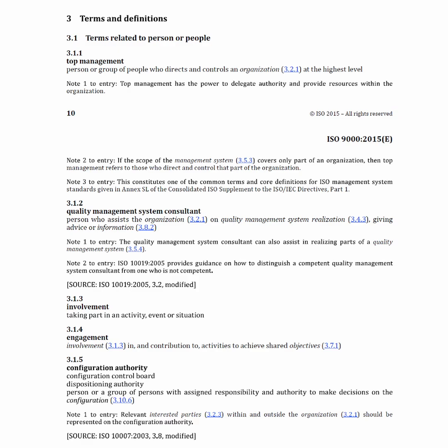Now, although the FDA is using ISO 13485 as the backbone of the new requirement, it is important to note that several components of 21 CFR Part 820 are still applicable. In addition to ISO 13485, manufacturers should also be aware that aspects of ISO 9000, specifically the terminology and definitions found in Clause 3, are also referenced within ISO 13485. So, as a manufacturer, when you're updating your references, you need to ensure that you're also updating your references to the ISO 9000 definitions. You should also verify going through that you're using the correct terminology.